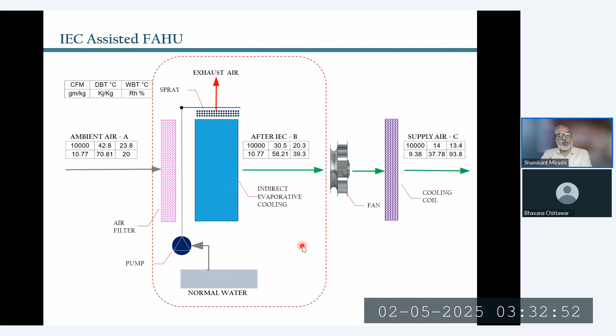We are looking at evaporative cooling in the best possible way combined with refrigeration cooling. When the air comes in, the sensible load is taken care of by one technology, and the latent load or moisture removal is taken care of by a different technology. Both technologies work at their best, and the result is a 30% energy saving.